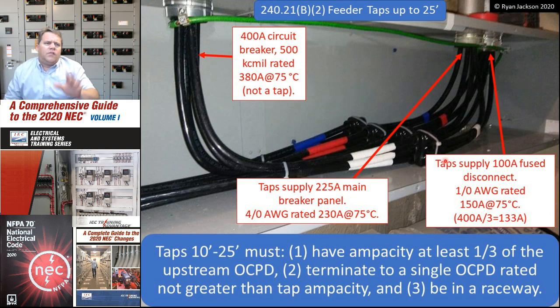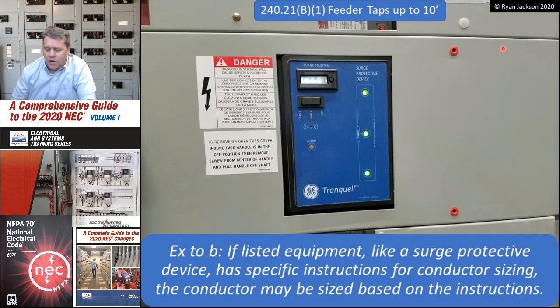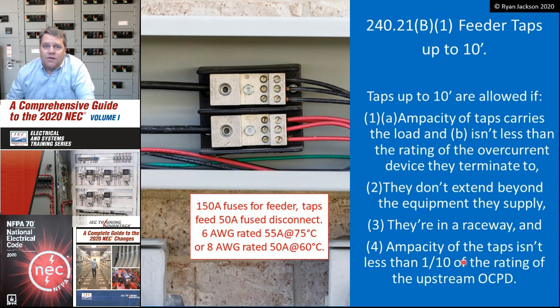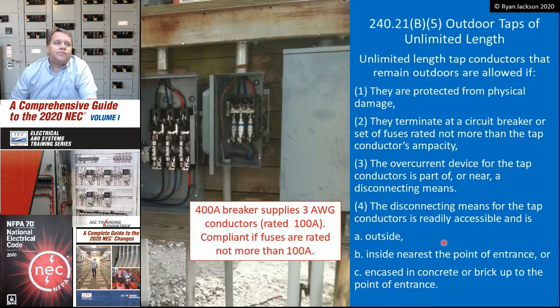Could I tap, for example, 14 gauge wire off of this 400 amp breaker and run it 100 feet? Well, no, because by the time you get 100 feet of 14 gauge wire, if you touch them together and try to trip a 400 amp breaker, it might not happen. You might not generate enough current to actually initiate that overcurrent device. So the longer we get, the more restrictive the rules get. So I'm limited to 1/3 the rating for a 25-foot tap, whereas on a 10-foot tap, I only have to worry about 10% of the rating of the upstream device.